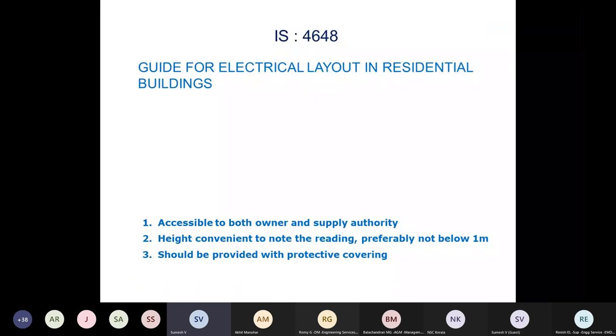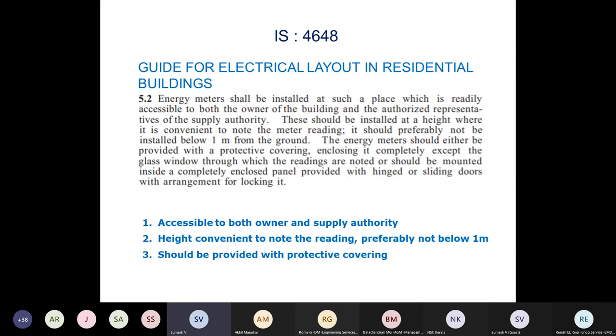IS 4648, about the general electrical layout of residential buildings, says the energy meter shall be installed at such a place which is readily accessible to both the owner and the supplier. That is, the meter should be accessible to both the owner and the supplier. Then the height should be convenient to note the reading. It should not be much higher or much lower; it should be about 1.8 meters. It should be provided with a protective covering. The meter should be provided inside a protective covering.